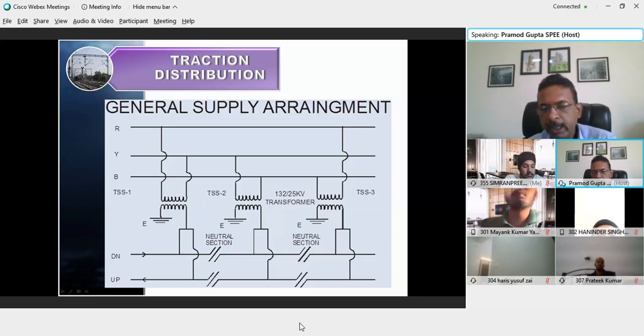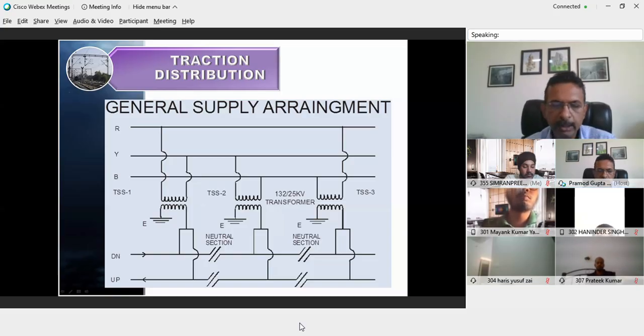Suppose I have taken my own TSS for maintenance. Similar to loco maintenance schedules, there are maintenance schedules where I have to shut down the power supply in the TSS and carry out maintenance. When I take the TSS for maintenance, the power supply in its feeding zone is not available. But I should have some alternative arrangement to feed the OHE, because I have not taken the maintenance block in the OHE. So I should be in a position to extend the power supply from the adjoining TSS.